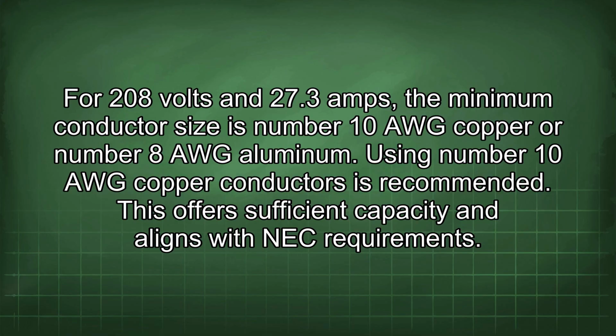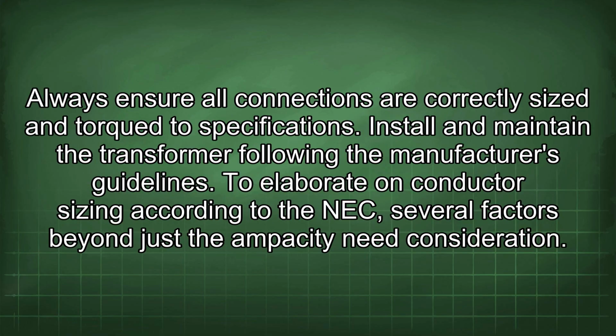Using number 10 AWG copper conductors is recommended. This offers sufficient capacity and aligns with NEC requirements. Always ensure all connections are correctly sized and torqued to specifications. Install and maintain the transformer following the manufacturer's guidelines.